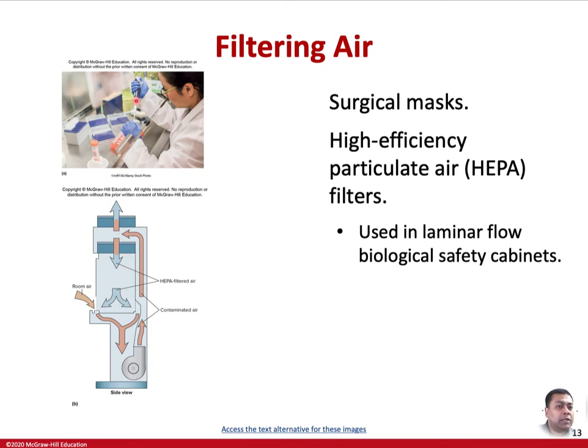So why do we call it a laminar airflow hood? Because this HEPA filtered air is creating a positive pressure, so nothing from the environment can come inside, even through the opening, because there is a positive pressure inside. And it is also recirculated, and extra air can go outside into the environment through a HEPA filter as well.